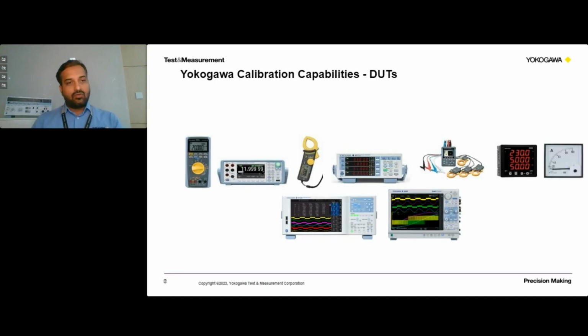So next, what are the capabilities we have from Yokogawa with respect to calibration? In this webinar, we are focusing on electrical parameters and pressure parameter. As you can see in the slide, these are the DUTs which we will be able to calibrate, and Yokogawa has the master products to calibrate all these DUTs. As you can see, multimeters and clamp-on meters, power meters, oscilloscopes, and panel meters such as panel indicators and analog voltage and current meters.